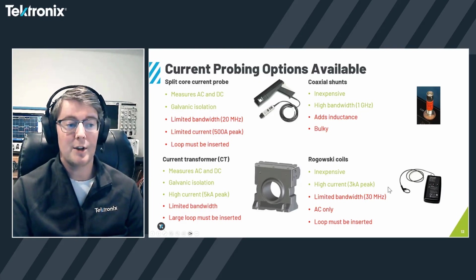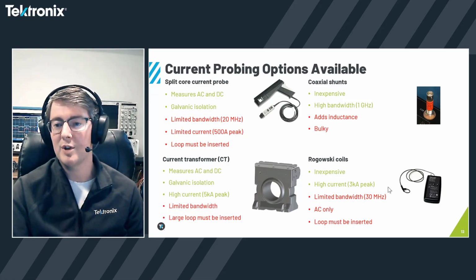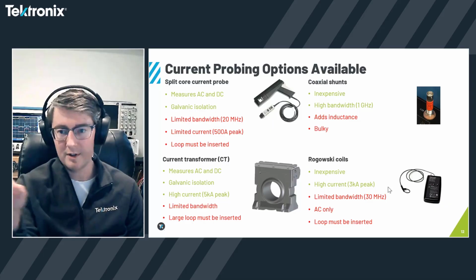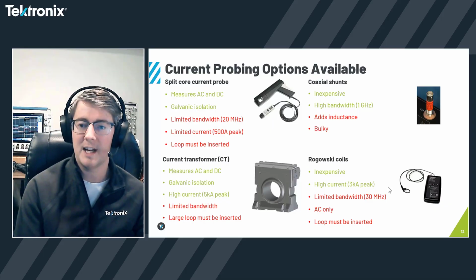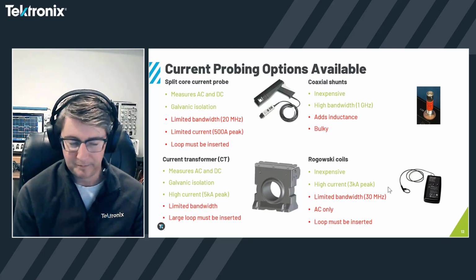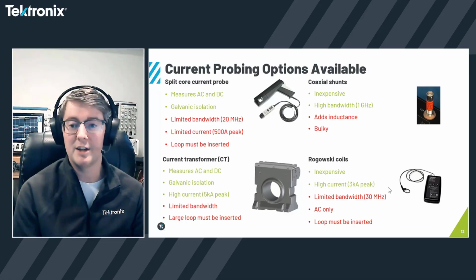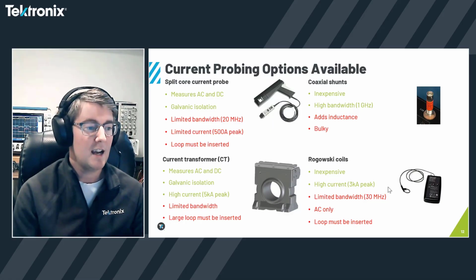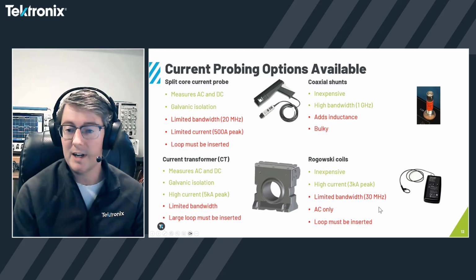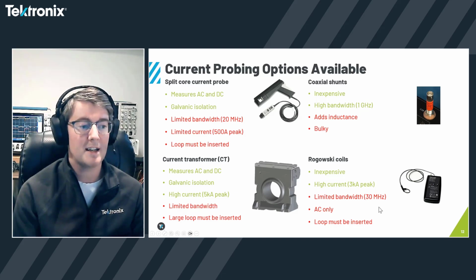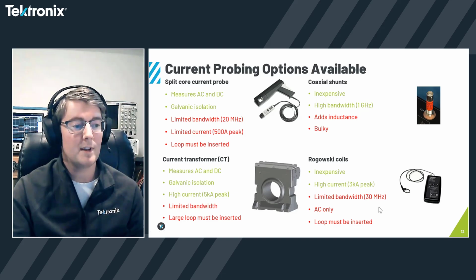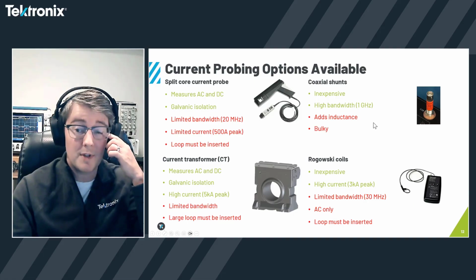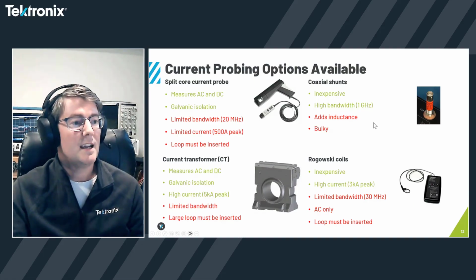Their challenges, though, are that they generally are limited in bandwidth, and so as we switch currents faster and faster, we're going to reduce the rise and fall time and muddle over what could be additional losses that we're missing. They're AC only, so they don't capture any sort of DC offset that might exist, and they of course introduce an additional loop that needs to be accounted for.